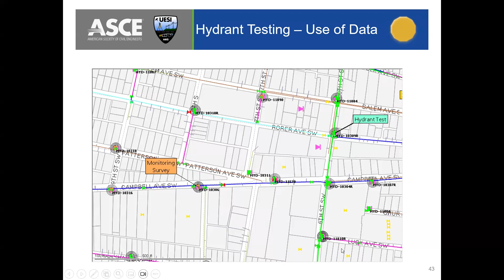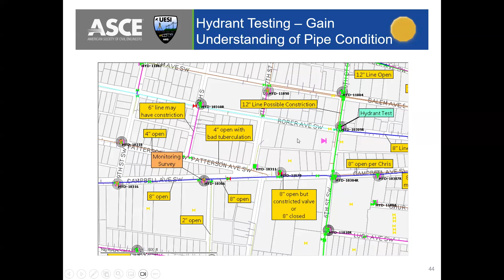And what we learned is that, for instance, when we flow this hydrant here, we can see that we're seeing a reaction in this hydrant, but it's not a huge reaction. So we know it's open, but there's bad tuberculation, but there's absolutely no change here. So then we know that this pipe may have a closed valve, or there might be some other constriction, or maybe the pipe was never even connected. But you can do this kind of analysis without even having a hydraulic model. But just something to consider there with the use of hydrant testing data.